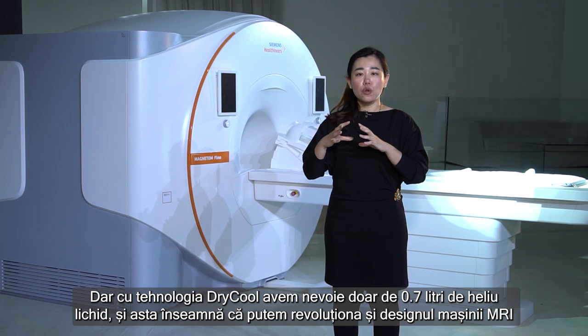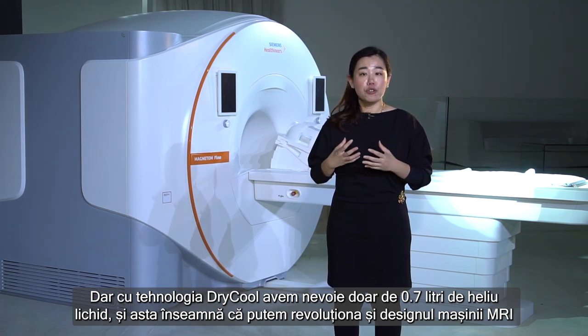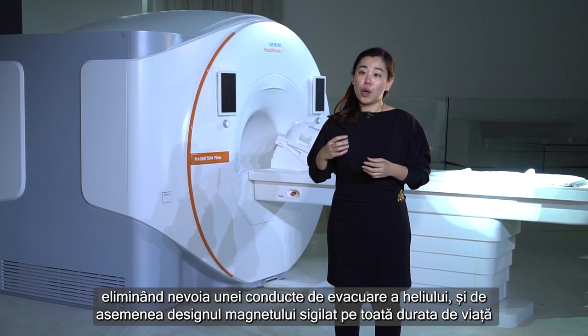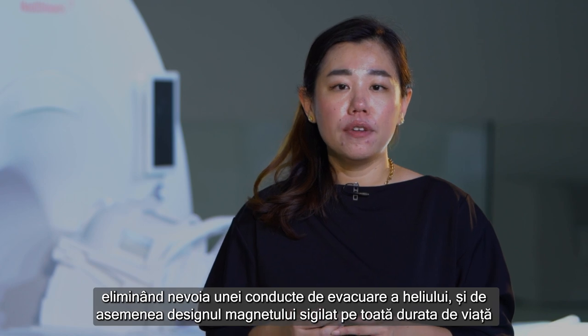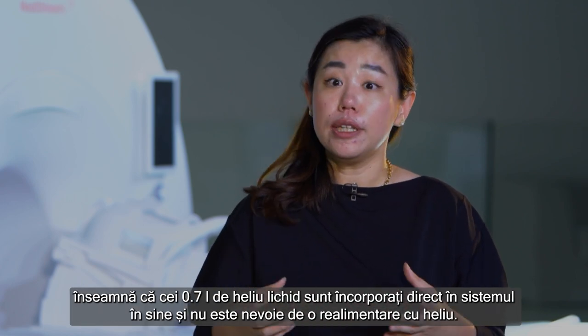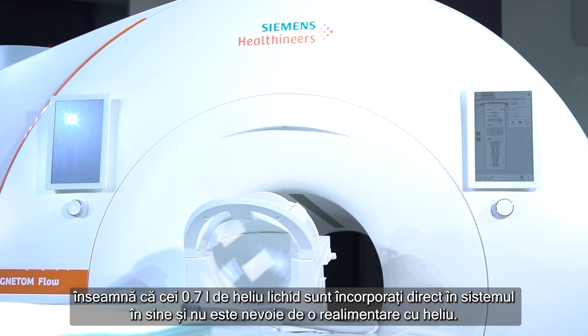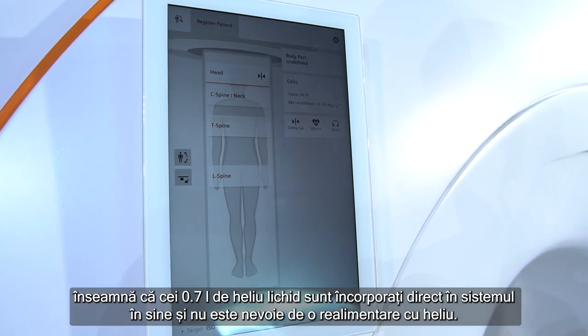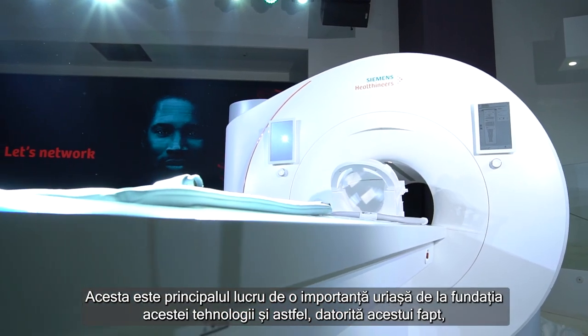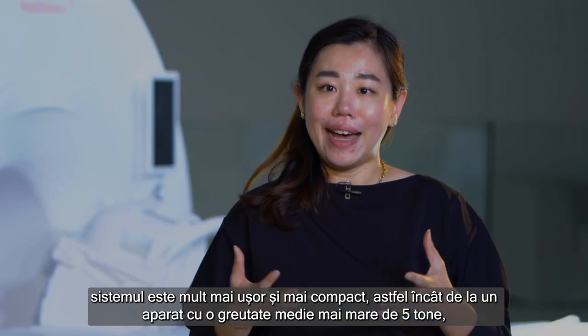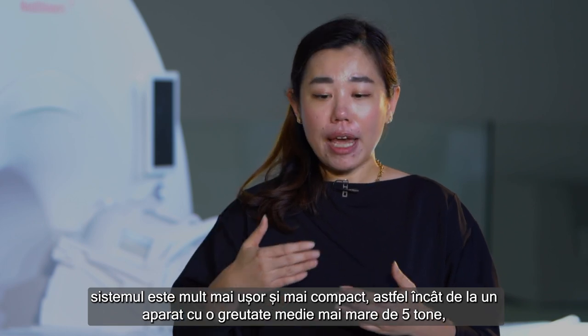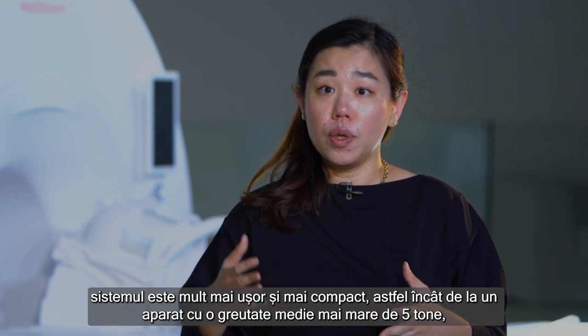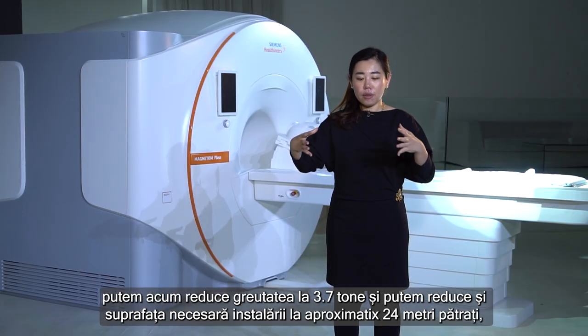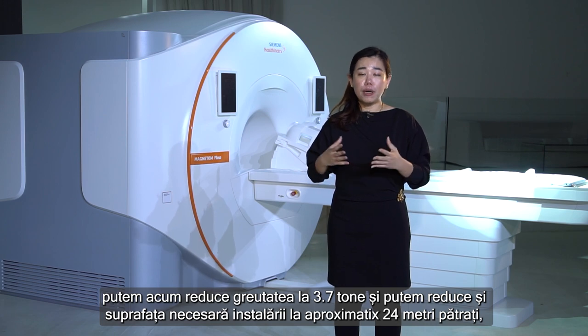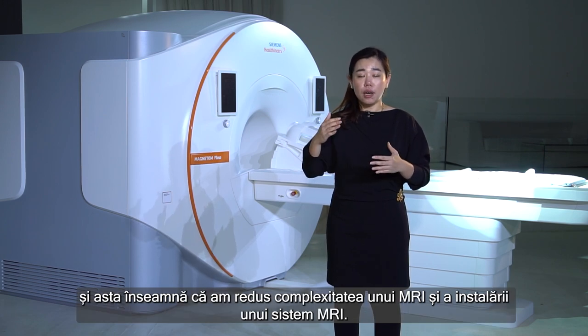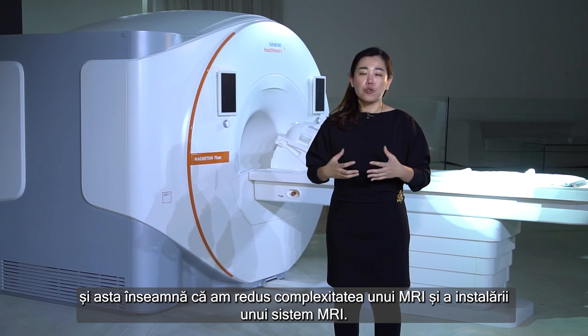This means we can also revolutionize the design of the MRI machine by eliminating the need for a quench pipe. It's also a sealed-for-life magnet design, which means the 0.7 liters of liquid helium is sealed directly in the system itself, so there is no need to refill helium anymore. That is one huge foundation. Based on this, the system is also much lighter and more compact - from an average of more than 5 tons in weight, we can now reduce to 3.7 tons, and reduce the footprint of installation to about 24 square meters. This really means we reduce the complexity of siting and installing an MRI system.